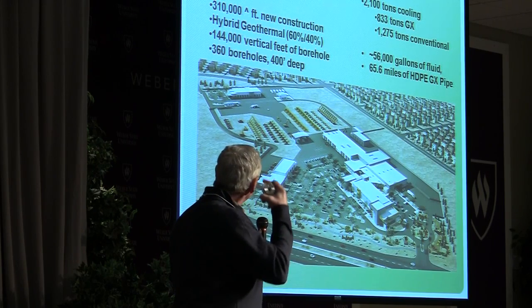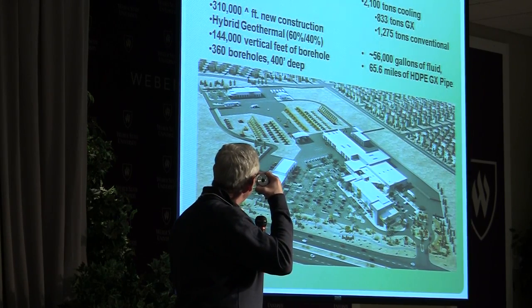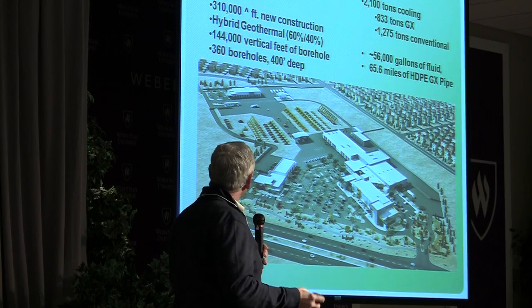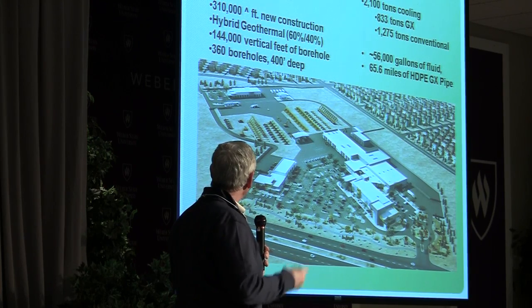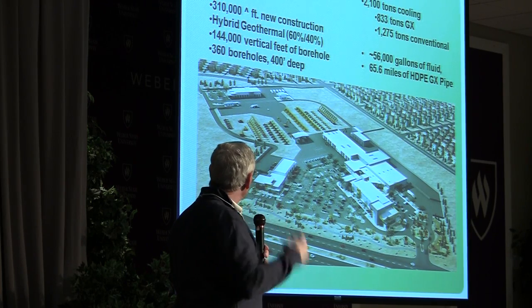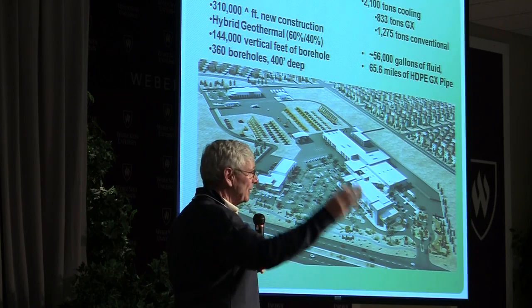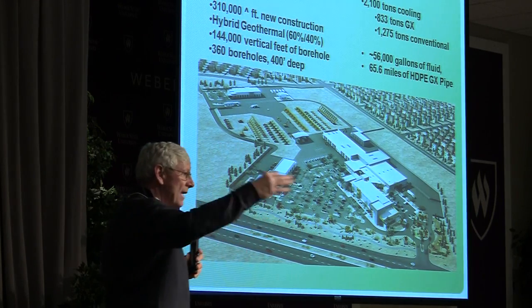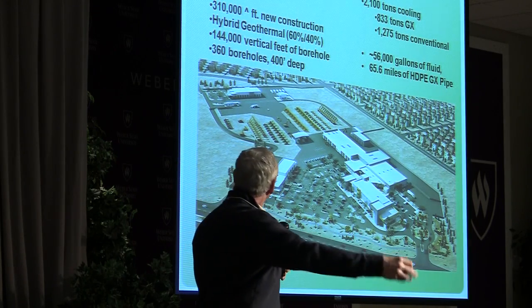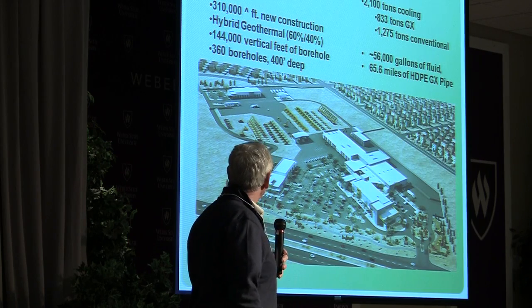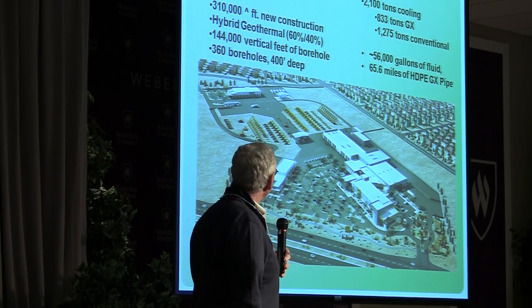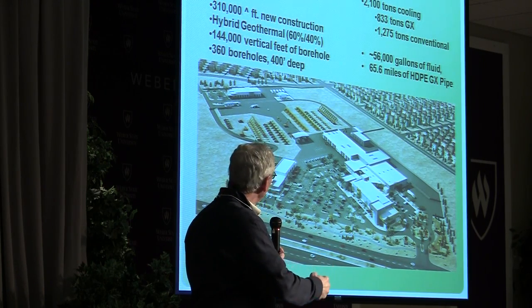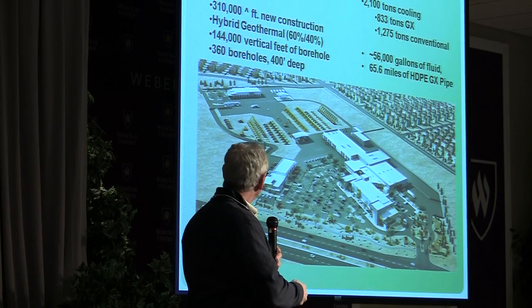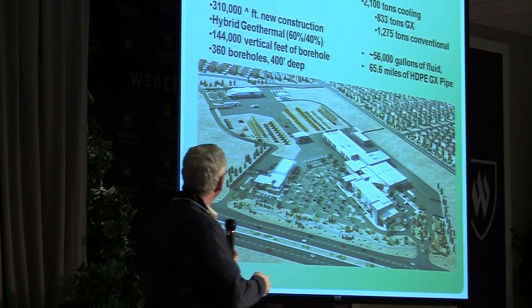We've got 65 miles of high-density polyethylene pipe buried in the ground, 310,000 total square feet of new construction. We did a hybrid geothermal of 60-40, meaning 60% renewable side and 40% conventional side, about 144,000 feet of borehole, and we're dealing with about 2,100 tons of cooling in the system, just to give you an idea of the magnitude of what we've got here.